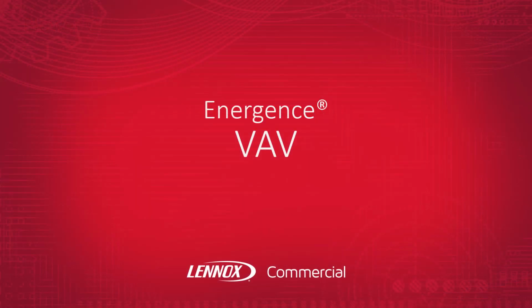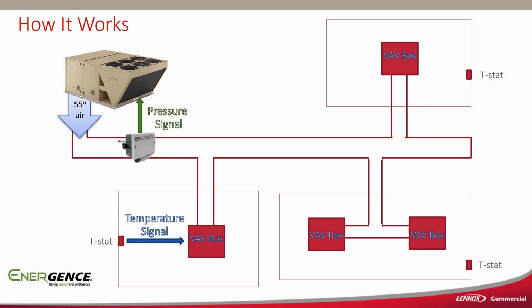We're going to briefly talk about the VAV system. Basically how it works, you have VAV boxes, either series or parallel boxes, and those boxes are basically dampers with a blower in them and typically reheat. They will be tied to a thermostat that will modulate those boxes open and shut, allowing the amount of air required to meet the space set point temperature.